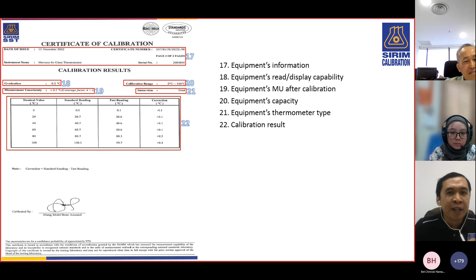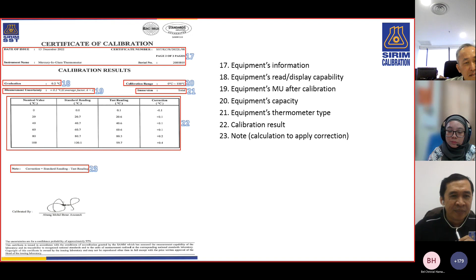Okay. Then, for example, how do you apply the correction? So we take this 20 degrees Celsius nominal value. The standard reading stated 20.7 degrees Celsius, while the test reading stated 20.6 degrees Celsius. And therefore the correction is 0.1. If you see the notes here, you can apply the correction directly to your equipment. It means standard reading minus test reading.